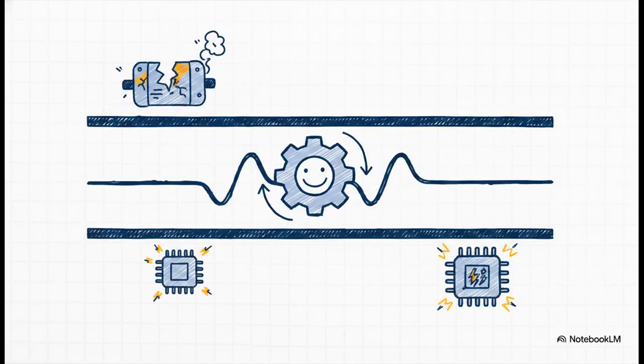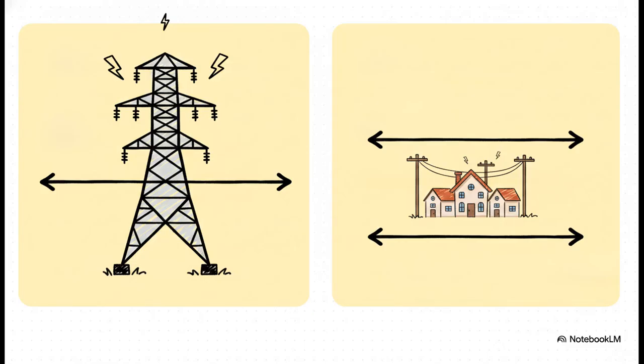The question isn't whether it drifts. Drift happens. The real question is how far it's allowed to drift under the transmission code before equipment actually starts failing. And here is the golden rule for steady-state conditions. 400 kV voltage is permitted to vary by only plus or minus 5%. Meanwhile, everything else, your 230 kV, 66 kV, 22 kV, 6.6 kV, and low voltage, they are all held within a slightly wider plus or minus 6% band.